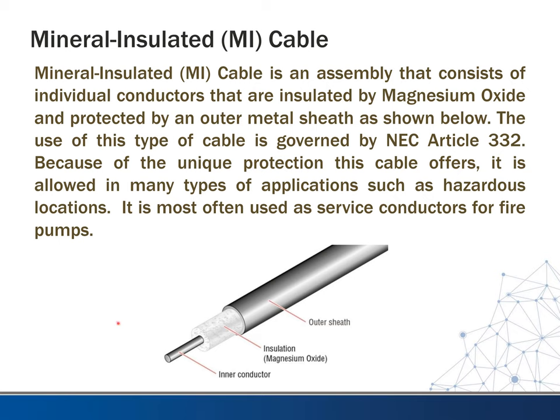Another type of cable is mineral insulated cable, or MI cable. This is an assembly that consists of individual conductors insulated by magnesium oxide and protected by an outer metal sheath. The use of this type of cable is governed by NEC Article 332. Because of its unique protection, MI cable is allowed in many types of applications such as hazardous locations and cable tray. Where you might see it most is on fire pumps — many jurisdictions will require MI cable to be run to the fire pump because it is so rugged, heavily protected, and fireproof.